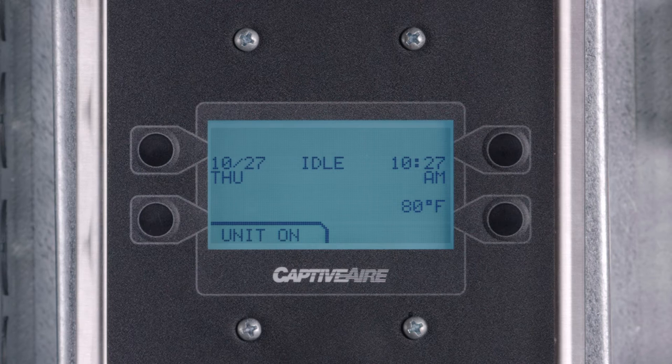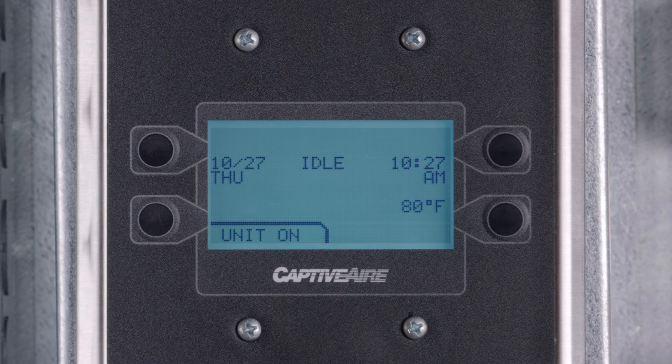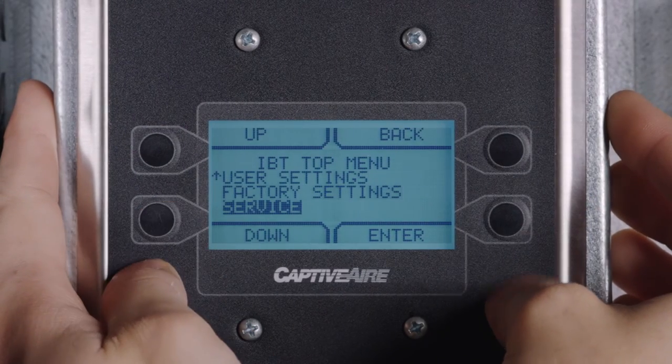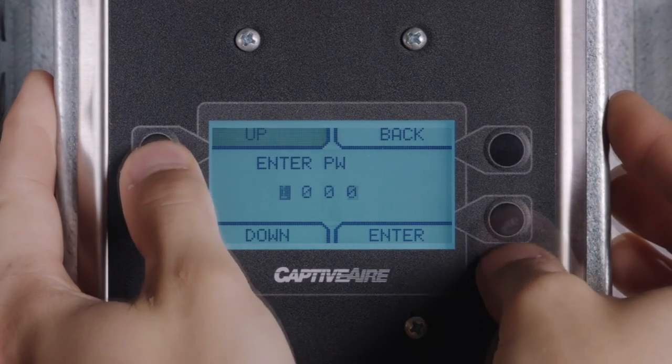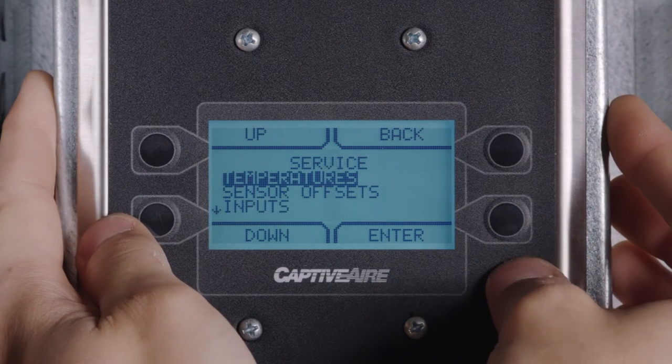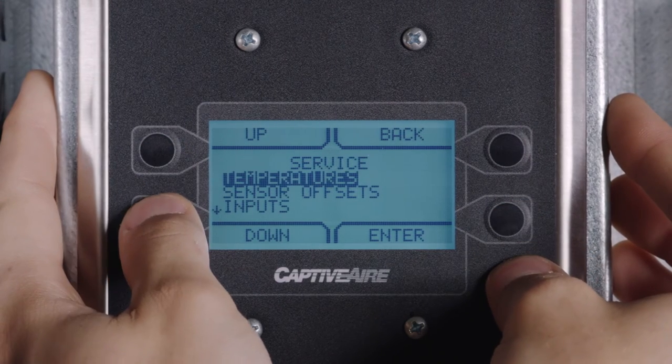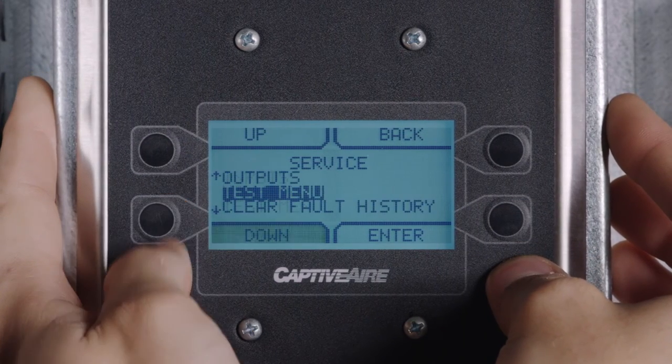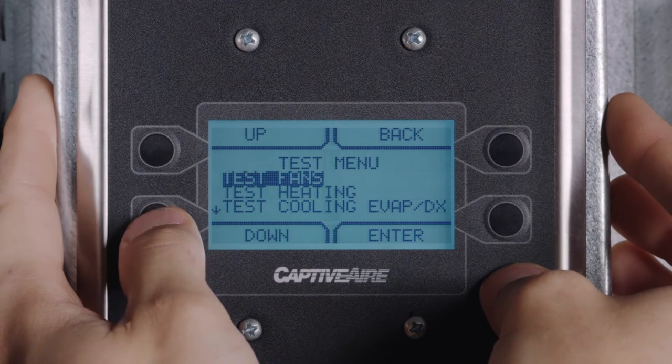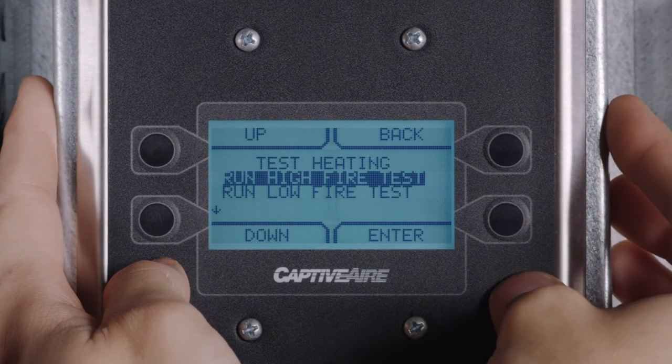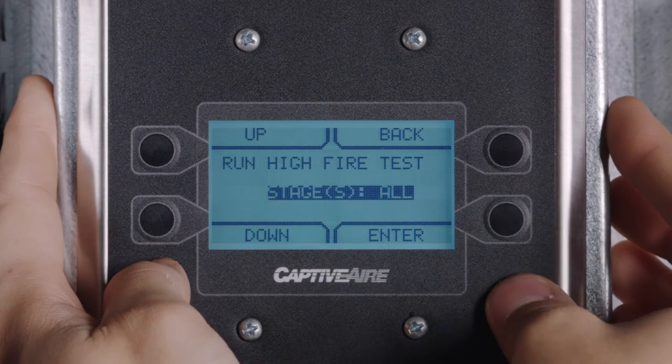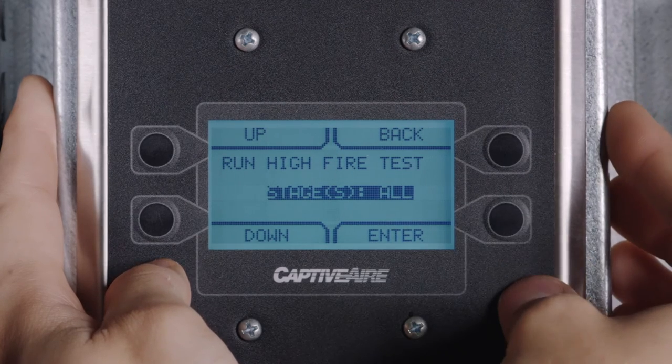Now you are ready to set your high fire pressure. This is achieved by configuring the HMI to high fire mode. First, access the menu, then select service, enter the password 1234, select test menu, test heating, run high fire test, stages, all.